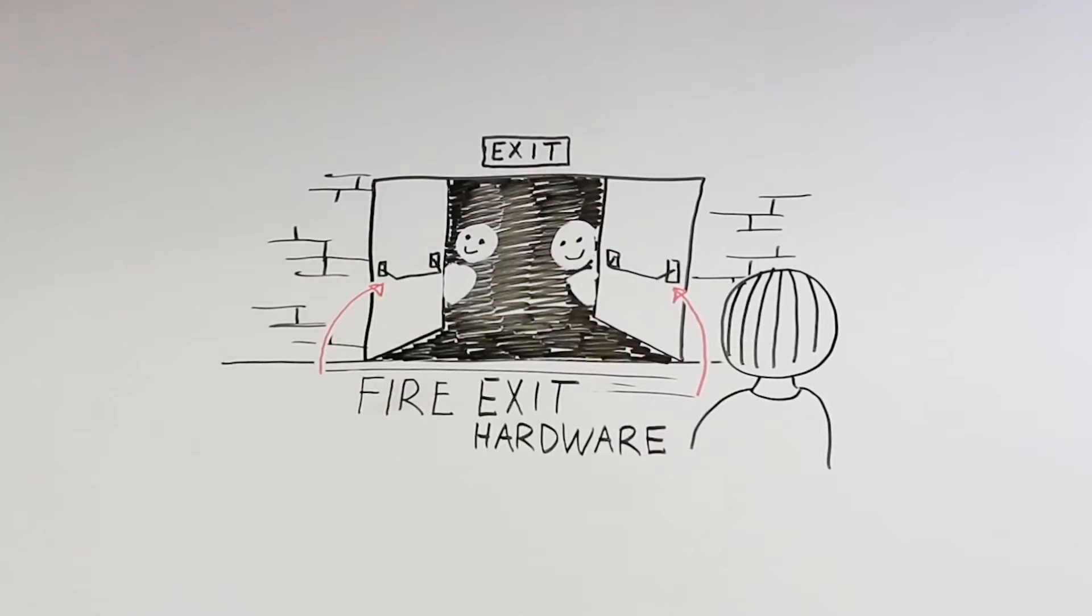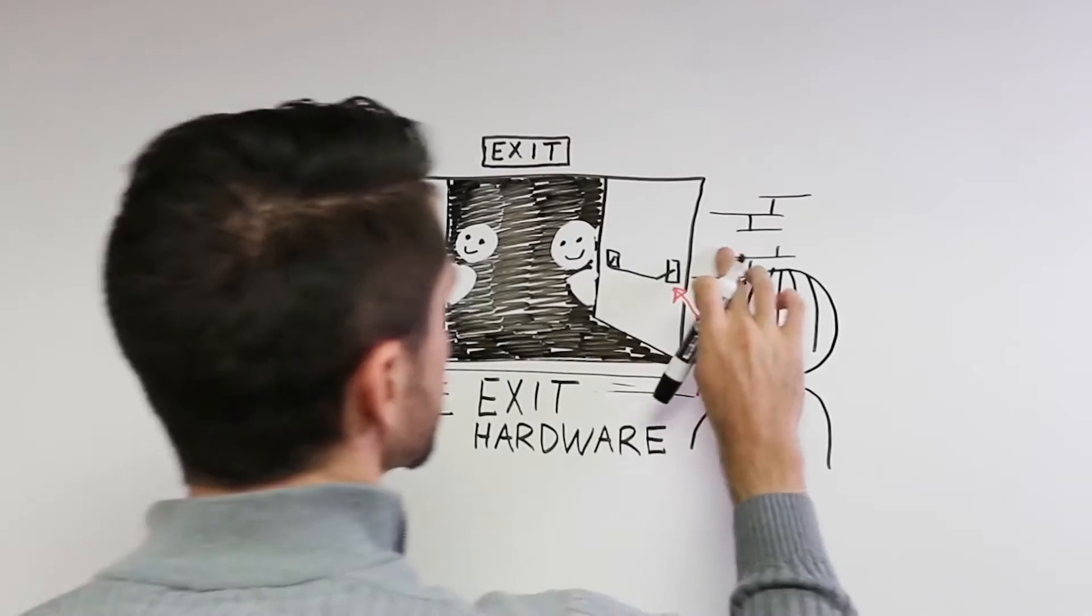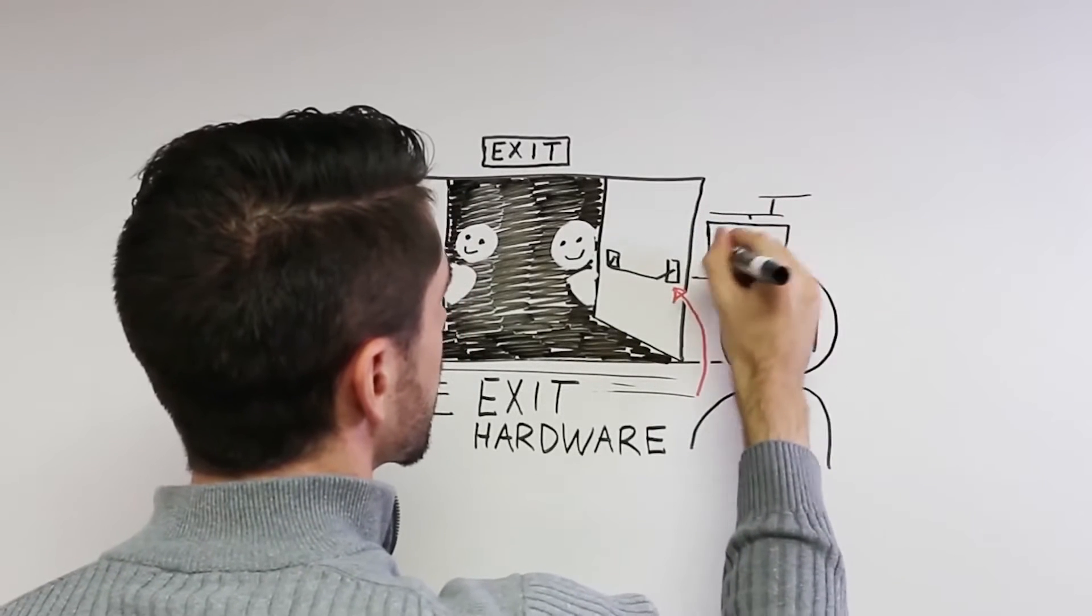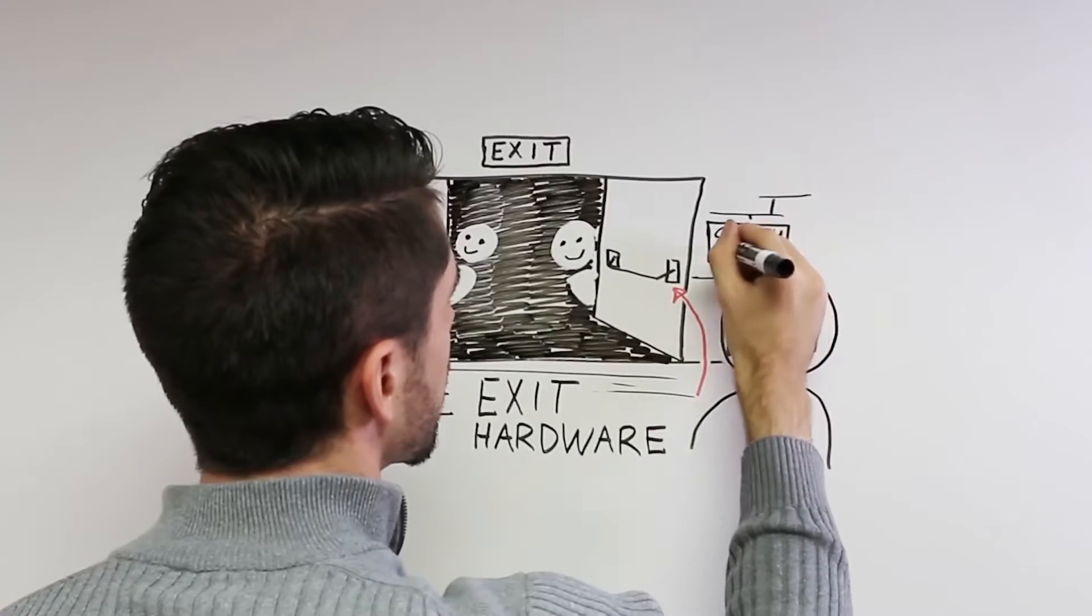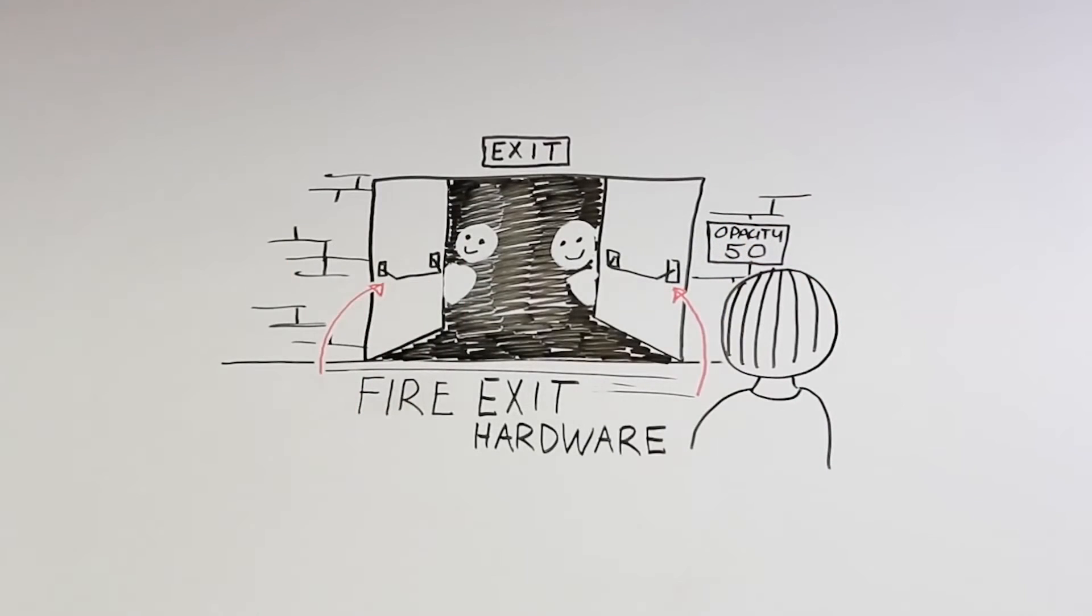Generally speaking, exit hardware is required for doors equipped with latches which serve rooms or spaces with 50 occupants or more in certain types of public buildings. Exit hardware is also required in some electric rooms.